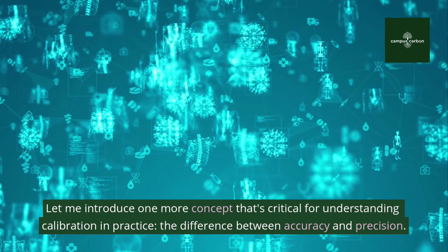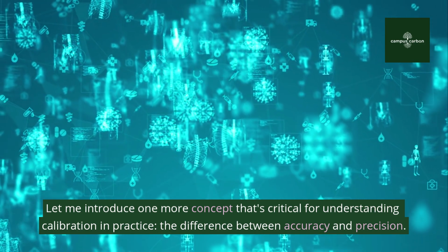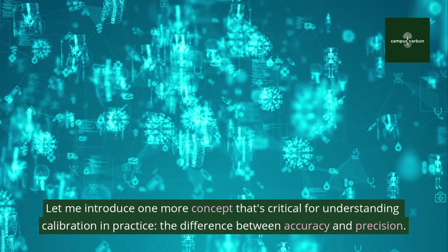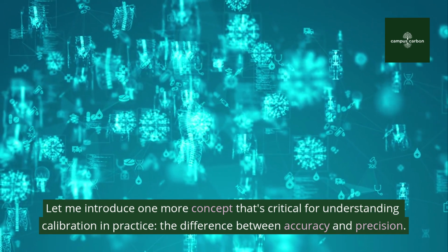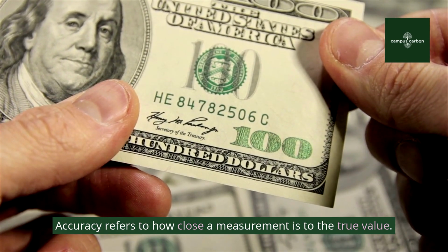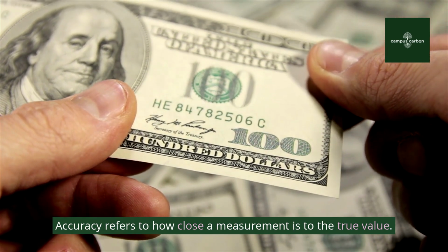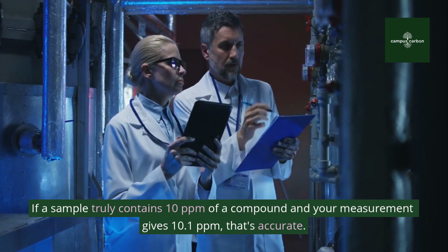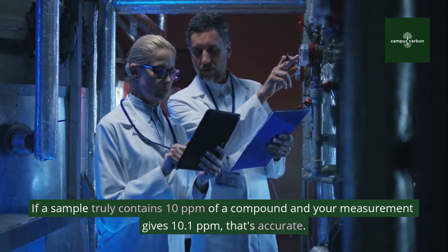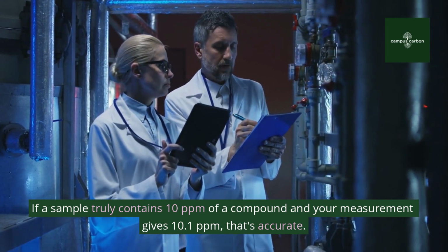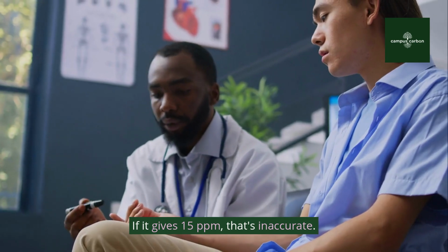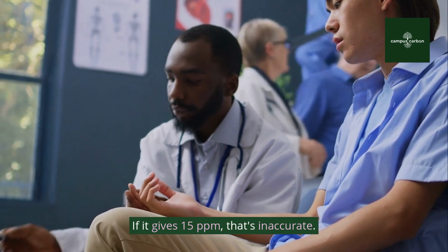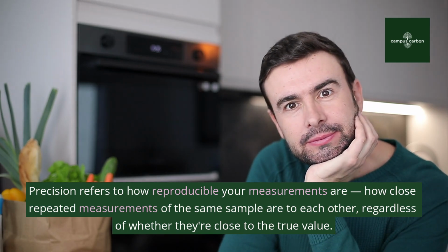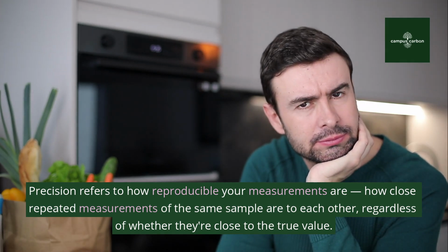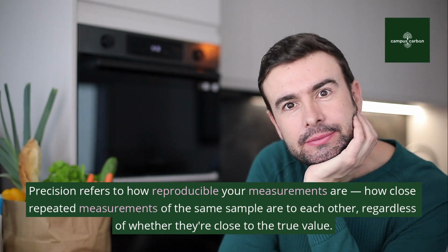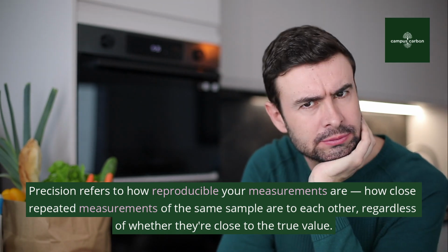Let me introduce one more concept that's critical for understanding calibration in practice: the difference between accuracy and precision. Accuracy refers to how close a measurement is to the true value. If a sample truly contains 10 ppm of a compound and your measurement gives 10.1 ppm, that's accurate. If it gives 15 ppm, that's inaccurate. Precision refers to how reproducible your measurements are, how close repeated measurements of the same sample are to each other, regardless of whether they're close to the true value.